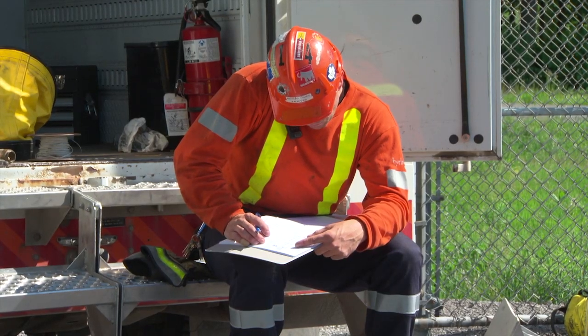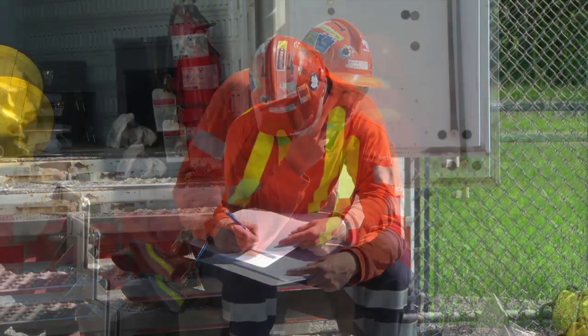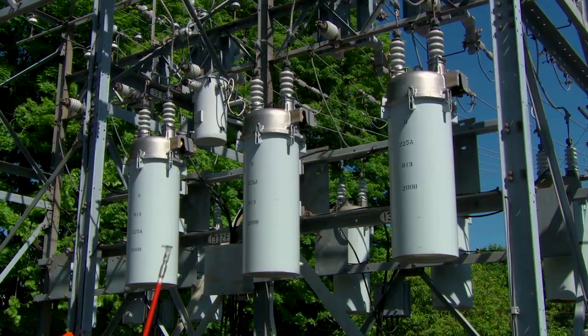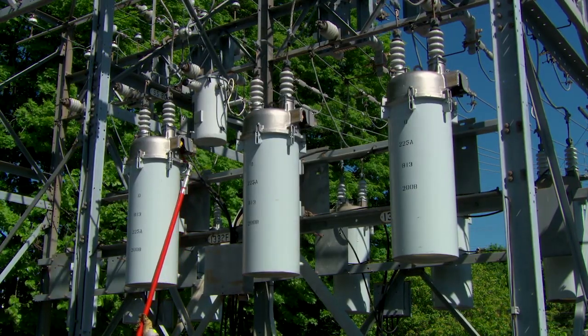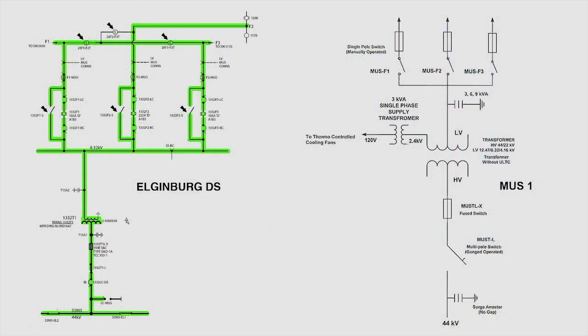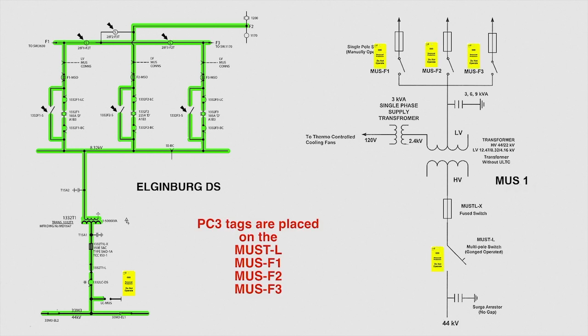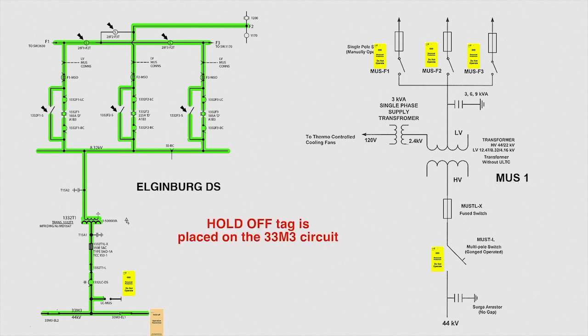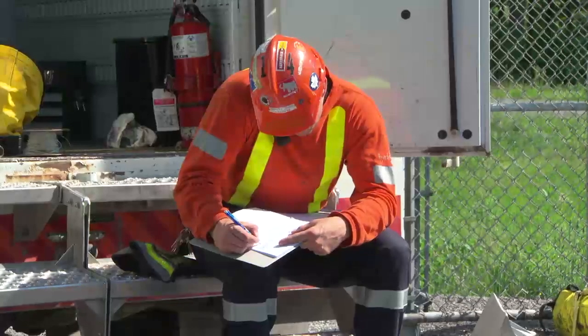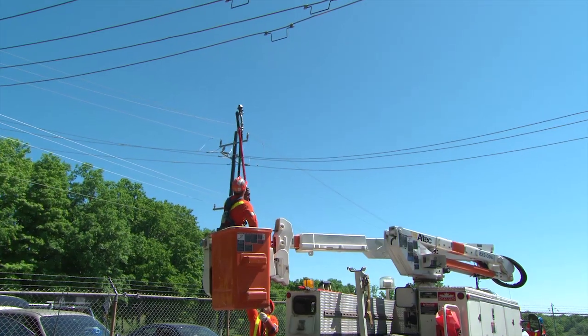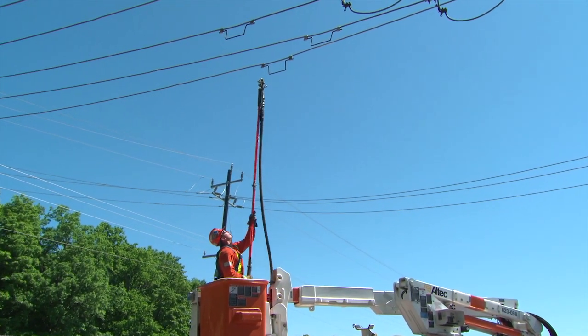Obtain a hold-off on the 44 kV circuit. This hold-off must remain in effect until all switching is completed. Place the station reclosers in the non-reclose position. Prepare and check an OTO for connecting the high voltage and low voltage cables to the DS.